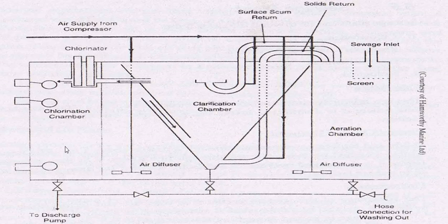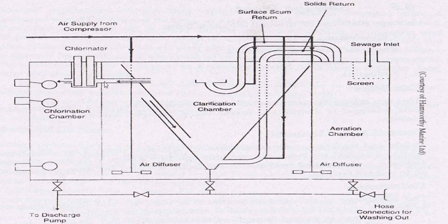We are going to discharge this liquid to the sea, so we need to neutralize the toxic substances and bacteria, because they will attack marine life. So we use this chlorination chamber and apply chlorine as a treatment for this sewage liquid.